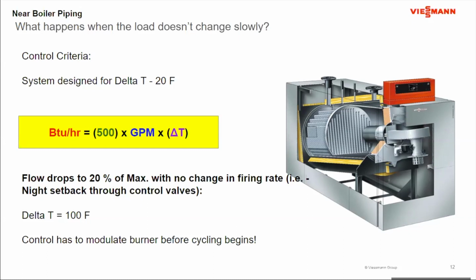So for instance, say I had a system where my system design temperature was a 20-degree delta T, through this formula in here, it's our BTU formula. We'll come back and reference this. It shows up in a lot of different presentations. But let's say I have a sudden change in flow rate from 100% down to 20% very quickly. In a hydronic system, how does this happen?